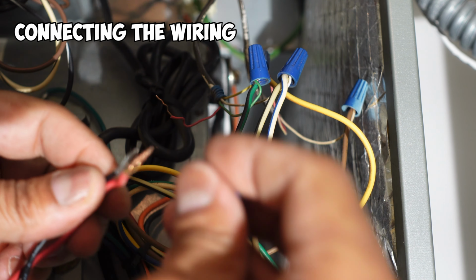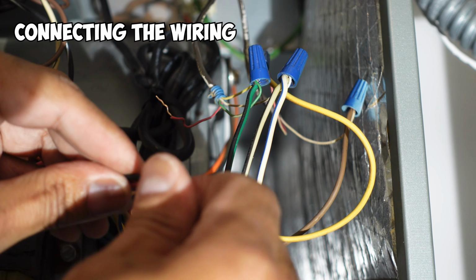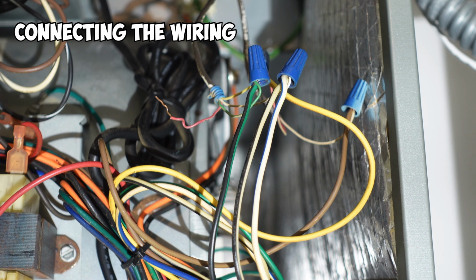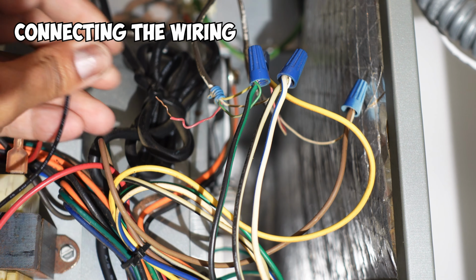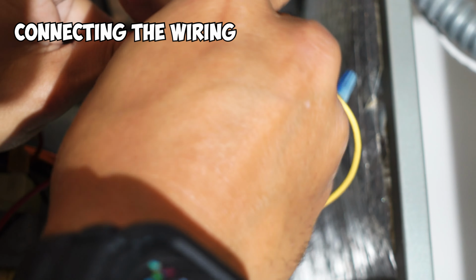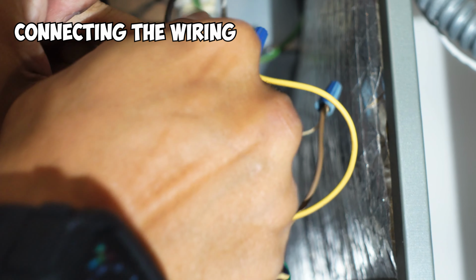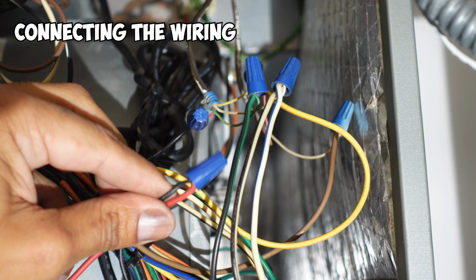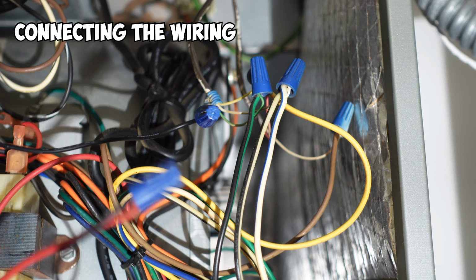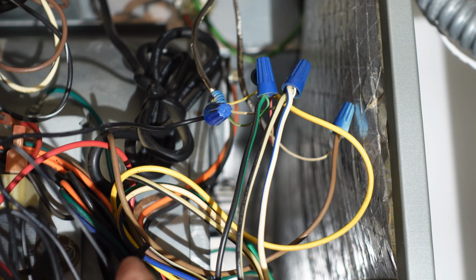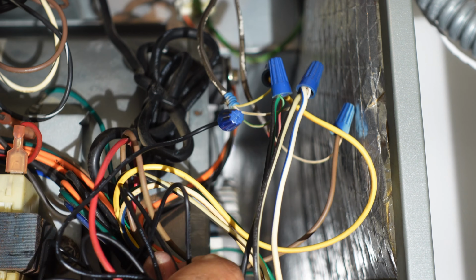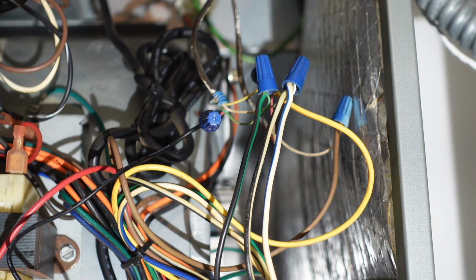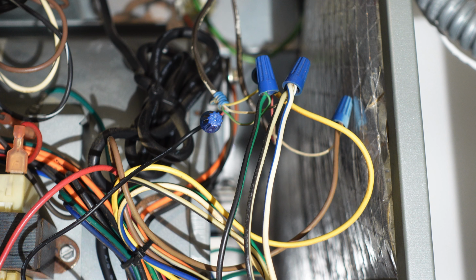What you want to do is connect one wire to one of the red wires, tighten it up with a wire nut, then connect the other red wire coming from your thermostat to the other end of the float switch. Tighten them up with a wire nut as well. And once you're done with that, the final thing is to tuck away your wires, zip tie any wires so that they're not dangling. And once that's done, we are ready to start the reassembly and putting back on our front panels.